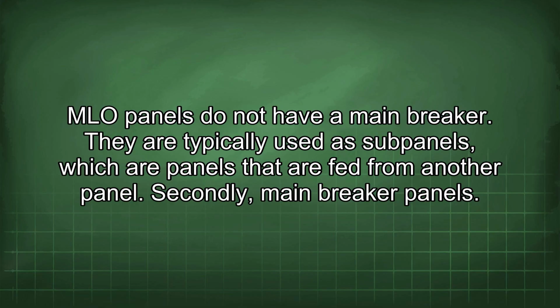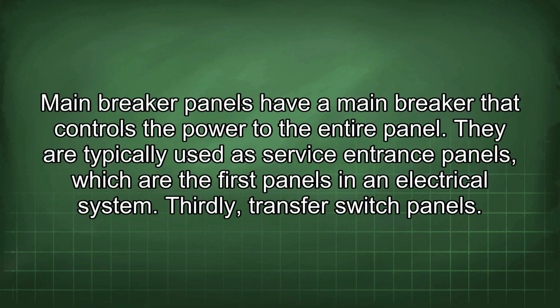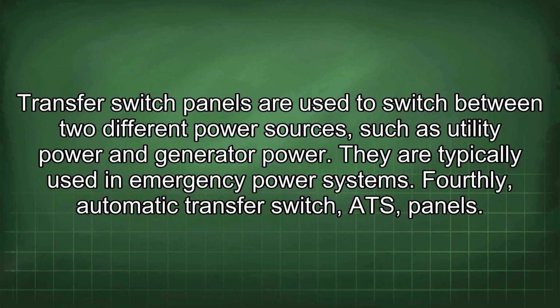Secondly, main breaker panels. Main breaker panels have a main breaker that controls the power to the entire panel. They are typically used as service entrance panels, which are the first panels in an electrical system. Thirdly, transfer switch panels. Transfer switch panels are used to switch between two different power sources, such as utility power and generator power. They are typically used in emergency power systems.